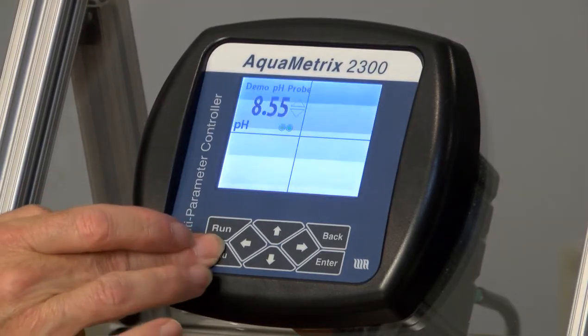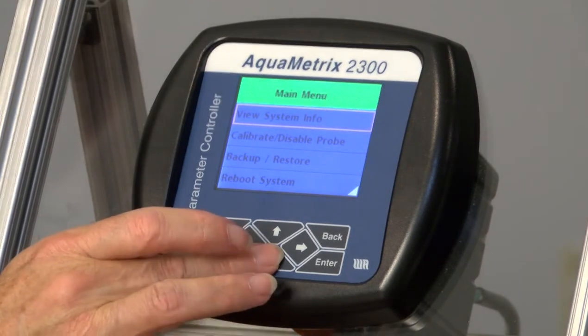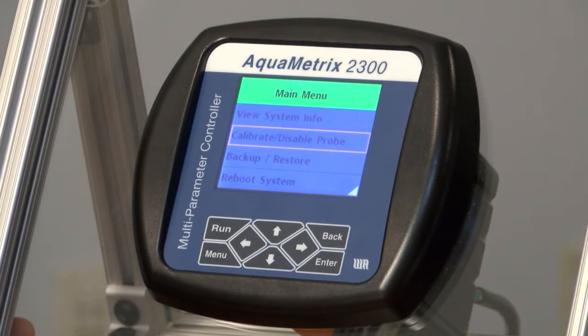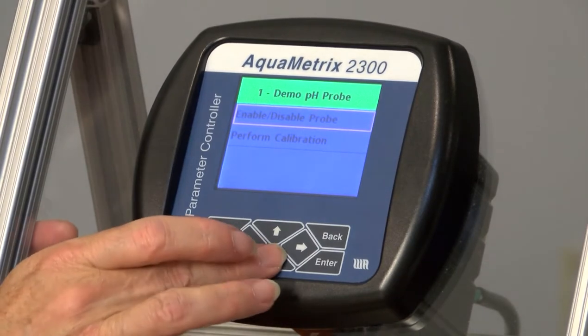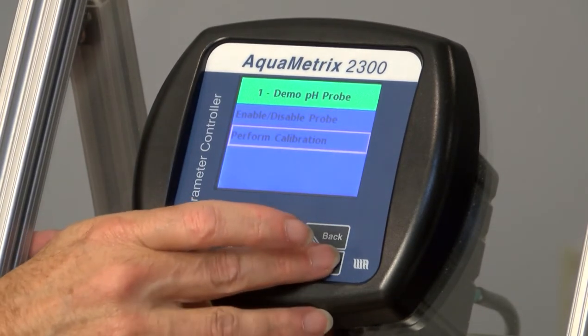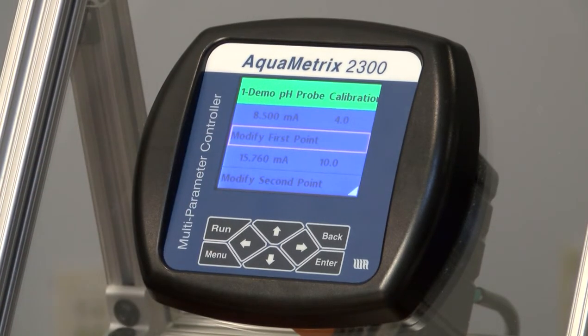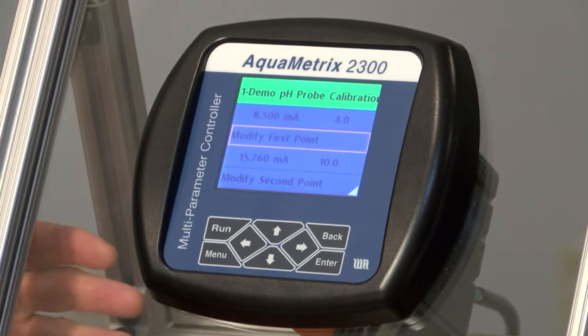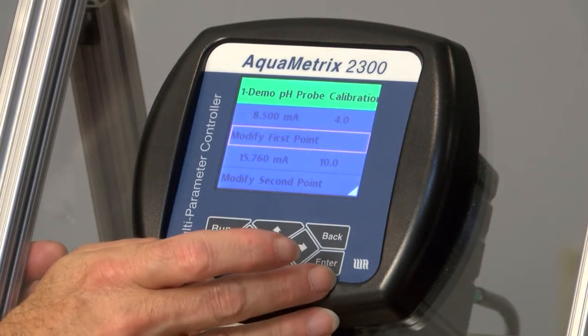Let's press the menu again to see what other options we have. The second menu item is very valuable. The Calibrate Disable Probe menu item allows us to calibrate using a 2-point calibration. Hit Perform Calibration, hit Enter, and you see the 2 points on the screen. Just follow the directions or read the manual, and that will guide you through a very common sense calibration procedure. That's a basic overview of the front panel. Once you set up the 2300 through the web interface, you can carry out day-to-day operation through the front panel, just as if it were any other controller.